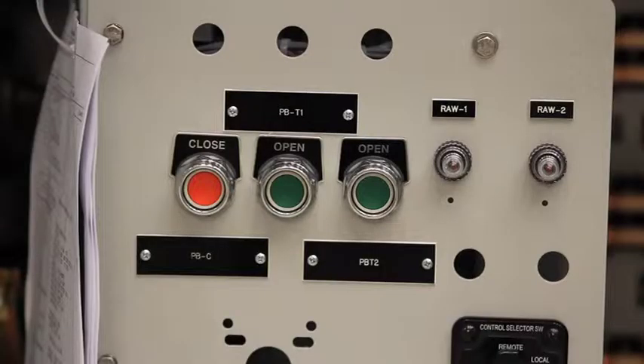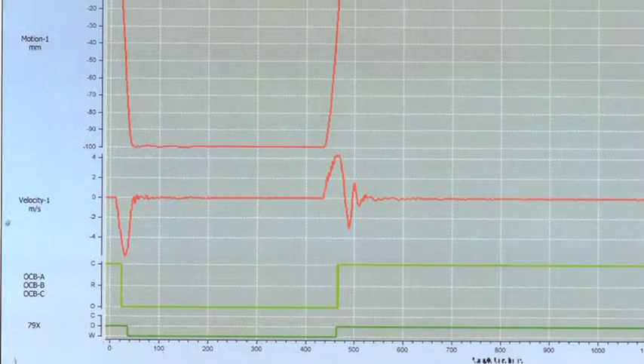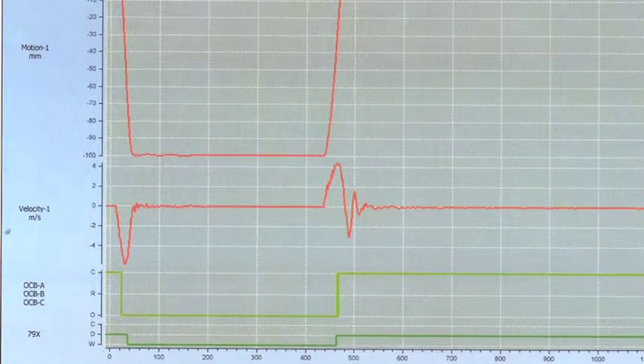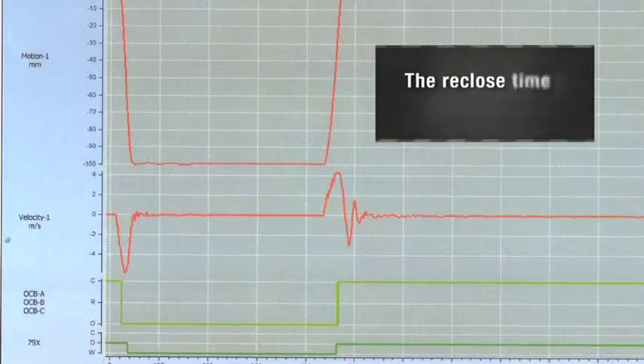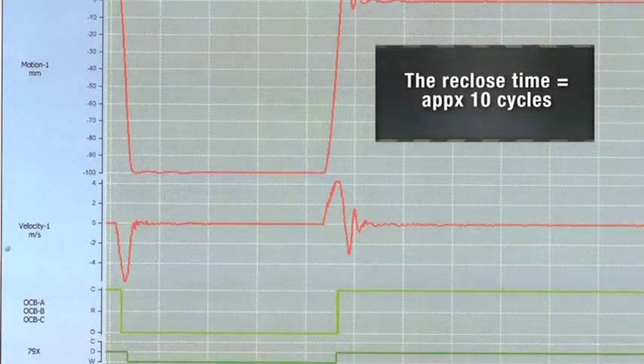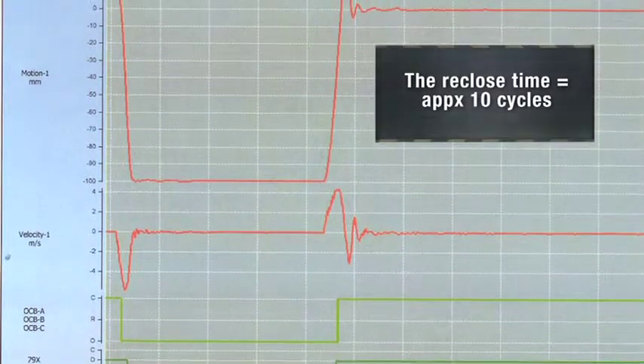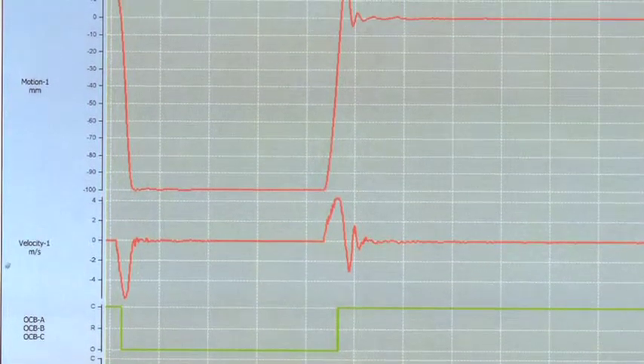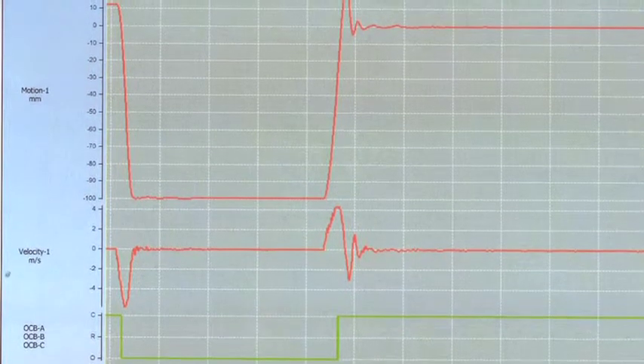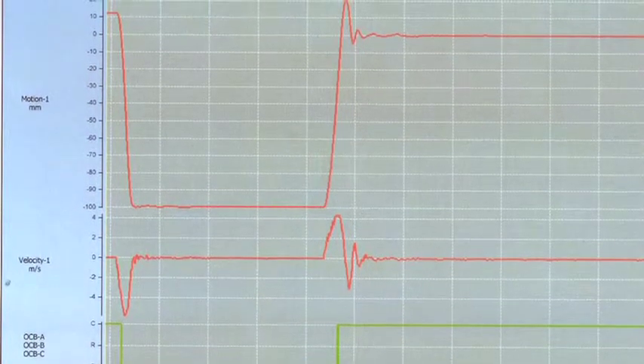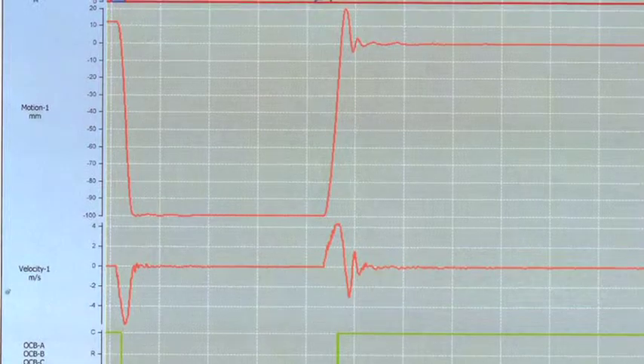Perform one open-close-open operation. Measure the reclose time and the end contact time. Unless specifically ordered otherwise, the reclose time will be approximately 10 cycles. If a special reclose time was ordered, an adjustable time delay relay will be provided. Adjust this relay if necessary to obtain the desired reclose time.